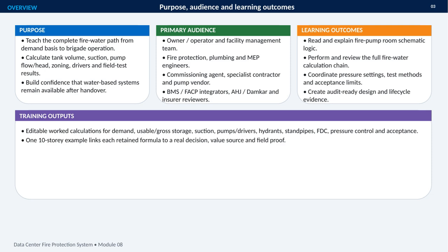By the end, participants should be able to read the fire pump room schematic, follow the full fire-water calculation chain, coordinate pressure settings and test methods, and create audit-ready design and lifecycle evidence. The key output is practical, editable worked calculations, including demand, storage, suction, pumps and drivers, hydrants, standpipes, FDC, pressure control, and acceptance. A 10-story example connects each retained formula to a real decision, its value source, and field proof.